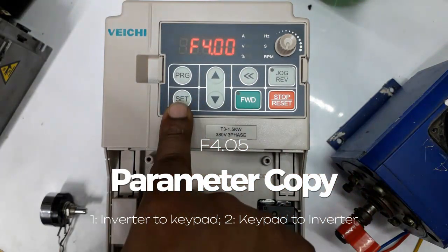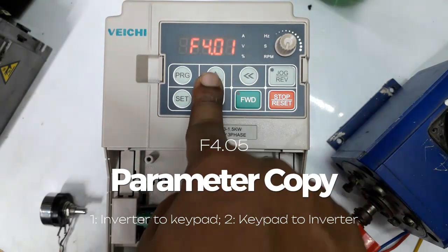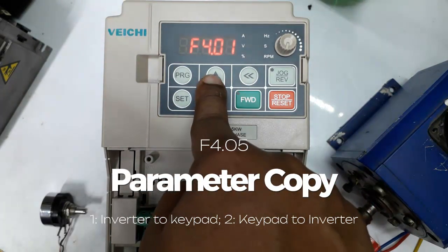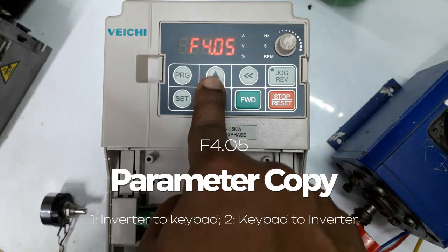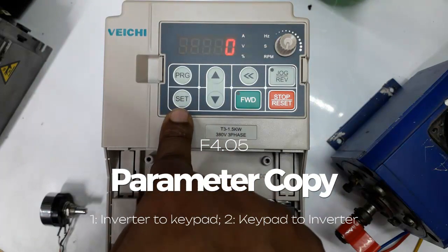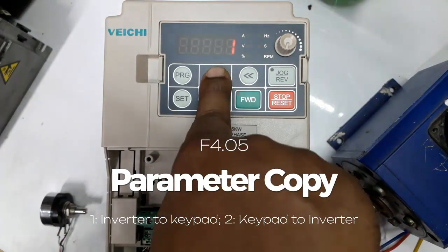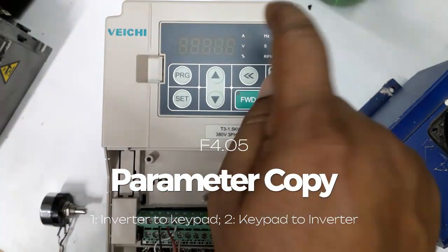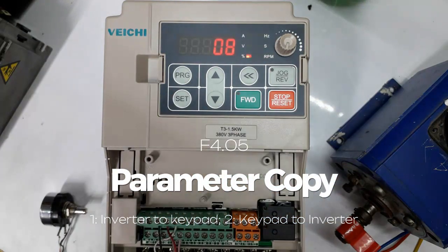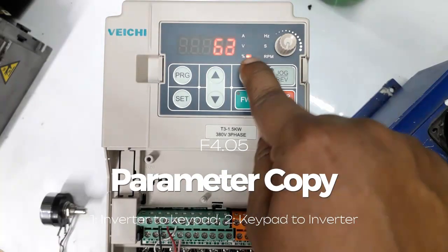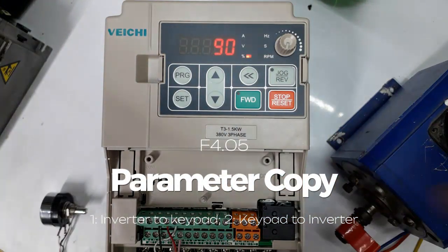So we need to copy parameters. Go to the parameter F4.05. Enter 1 here to copy parameters from inverter to keypad. The copying percentage is displayed. The parameter is copied from the inverter to the keypad.